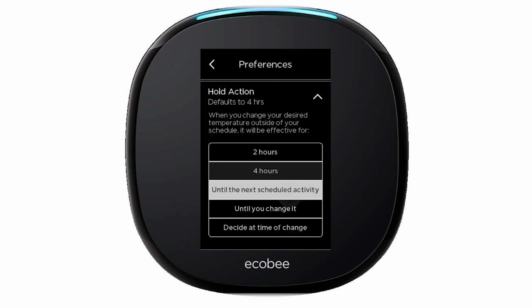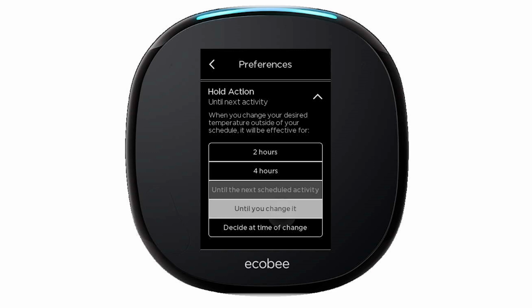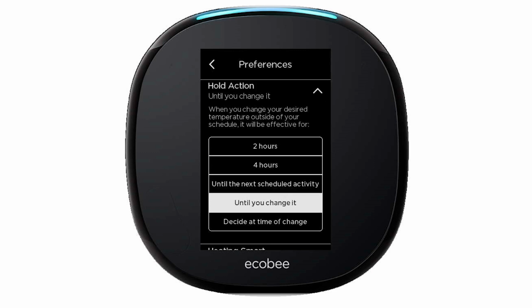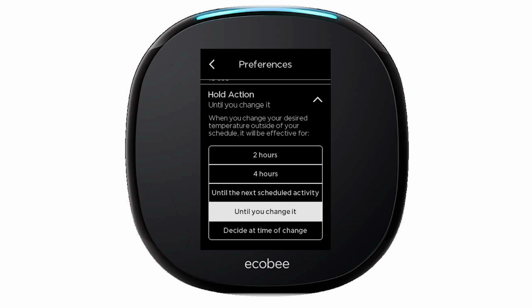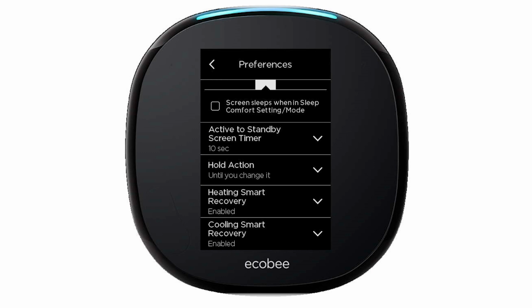Well, if you use this option, it's going to revert back to the next scheduled event. You can use the option to indefinitely hold it. You can even have it decide, so it's going to ask you when you change the set point how long you want to hold it. So a few different ways to manage that.